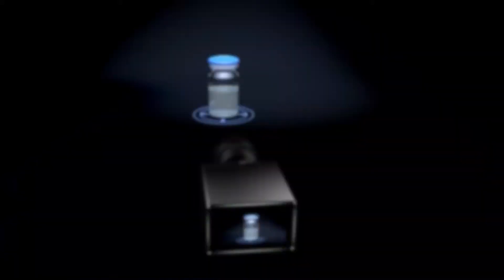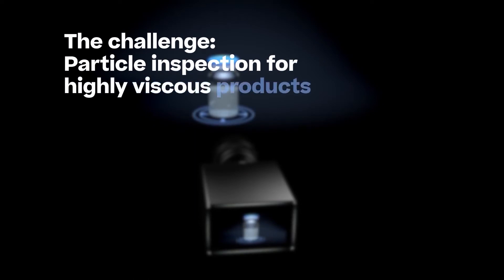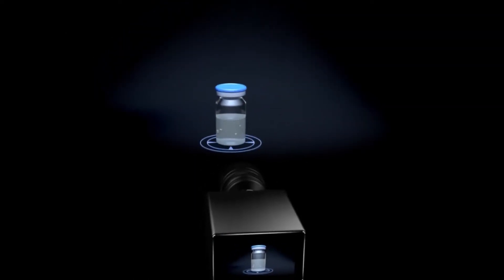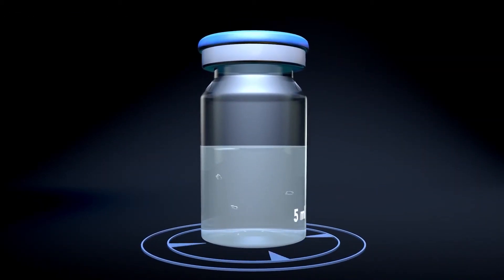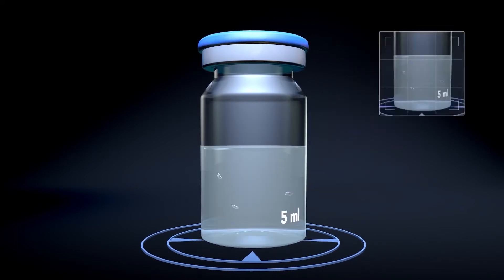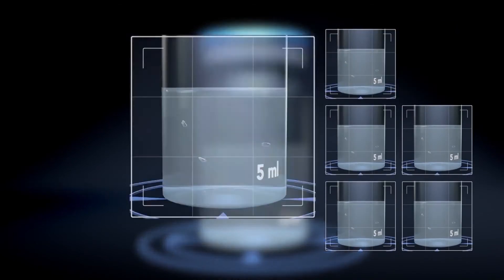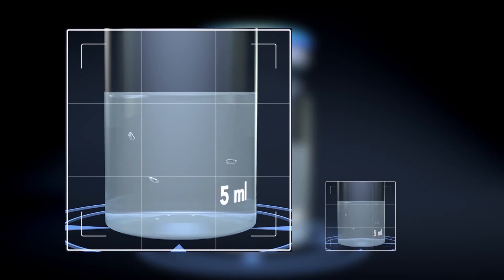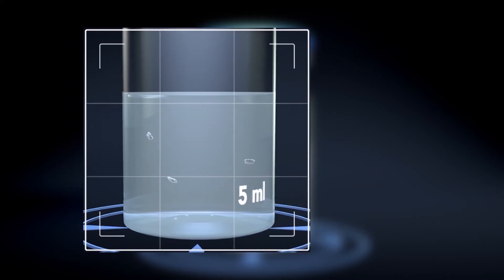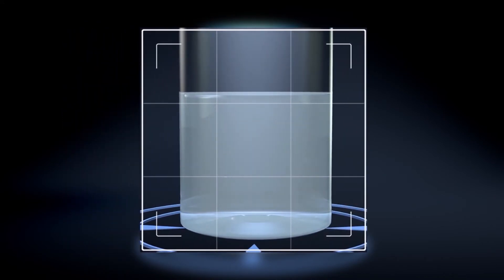The challenge: particle inspection for highly viscous products. When inspecting highly viscous products, the described inspection method produces no results since the contents of the container cannot be set in motion by rotation. Since there are no changes in particle position between the images, impurities inside the container cannot be differentiated from those on the outside.